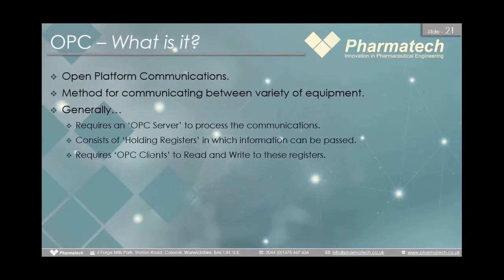The way that we tend to communicate is between the blender's IPC, industrial PC. We'll use a method of communication called open platform communications, or OPC. This is just a method for communicating between a variety of equipment, and it generally requires an OPC server, which is a piece of software installed anywhere, whether that be on the domain, on the blender's PC, or on your NIR control PC. And it basically consists of a set of holding registers in which information can be passed back and forth.